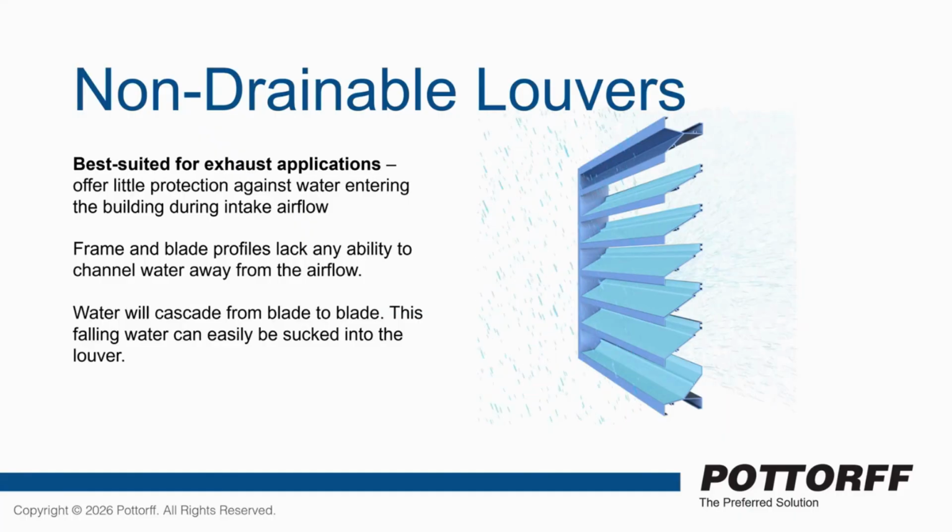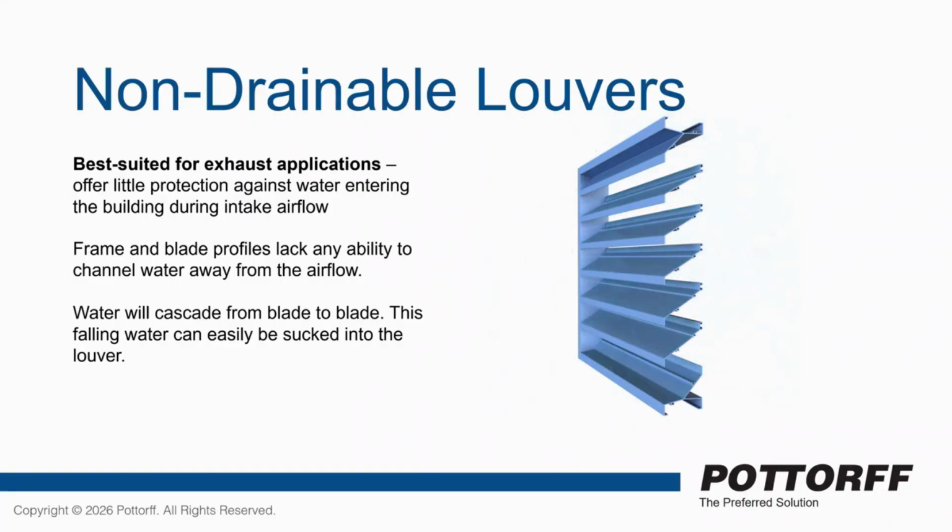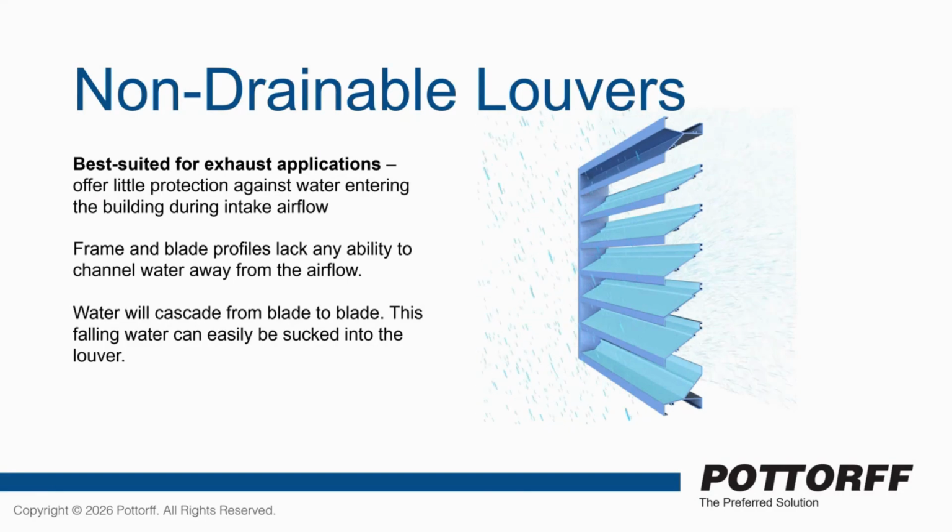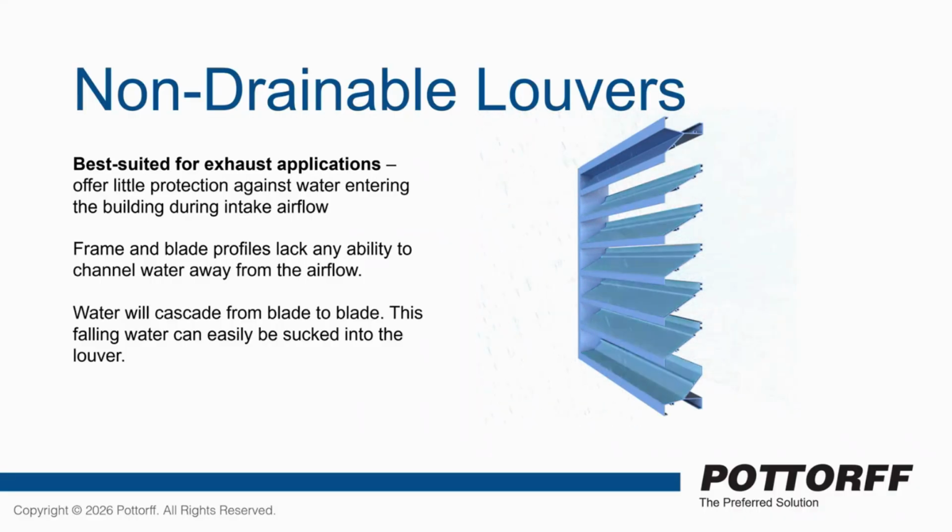And really, Josh actually here, he does have lots of experience in various jobs in the industry, but one of those actually was doing a lot of testing at AMCA. And we can probably say that what we'll typically see is the taller the louver, the better the chance of getting water into the building, and predominantly it's because the bottom blades are starting to catch a lot of water cascading down the further you go.